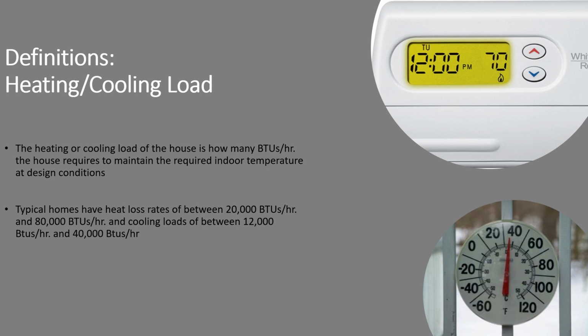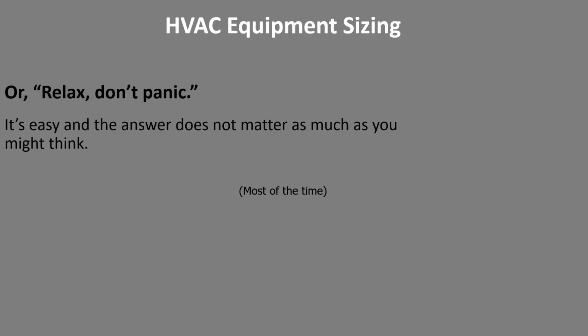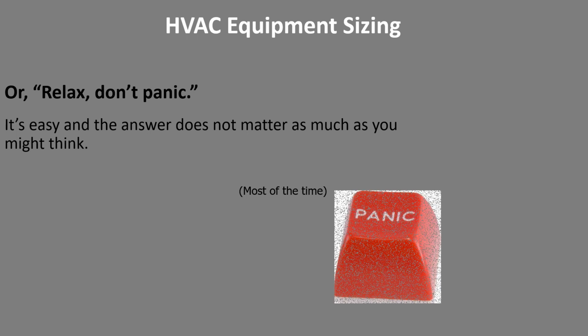When we refer to a heating or cooling load, really what we're referring to is how many BTUs need to be removed or added to the house to maintain indoor comfort at design conditions. Typical homes have heat loss rates between 20,000 BTUs and 80,000, and cooling loads between 12,000 and 40,000. Of course, a lot of homes will fall outside of that range. So when it comes to actually sizing the equipment, again, it assumes that we've done our heat loss and heat gain calculations. Most of the time, we get to relax.